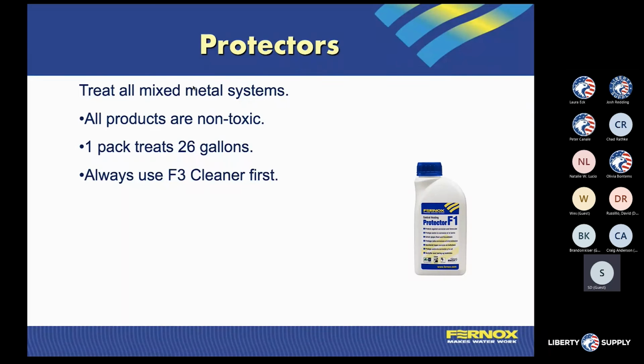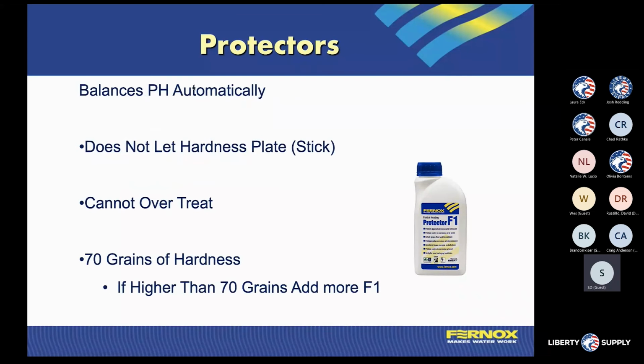It also auto balances your pH, which means if my pH is too high, it will lower it, and if it's too low, it is going to raise it. And again, you can't overtreat. So if I needed to put in a gallon or 3 pints or whatever the math came out to be, and I want to add a little bit extra, it's not going to harm the system and it's not going to send any of the chemistry off. So you're not going to have to worry about that. We're going to balance our pH, and we're not going to allow the hardness to plate. So this is going to be our overall component product from that standpoint.